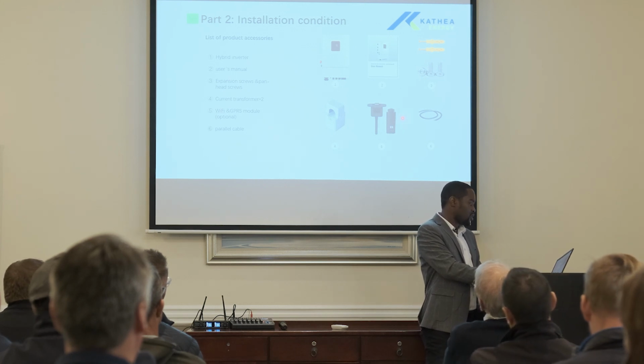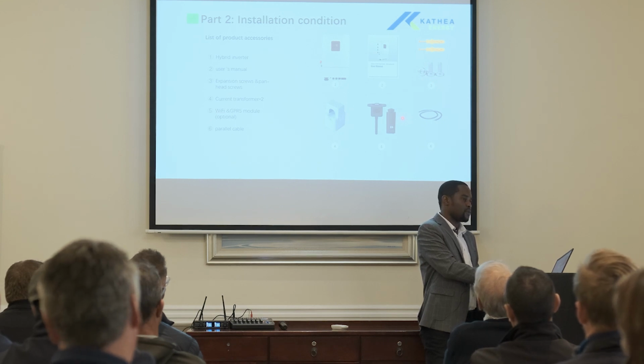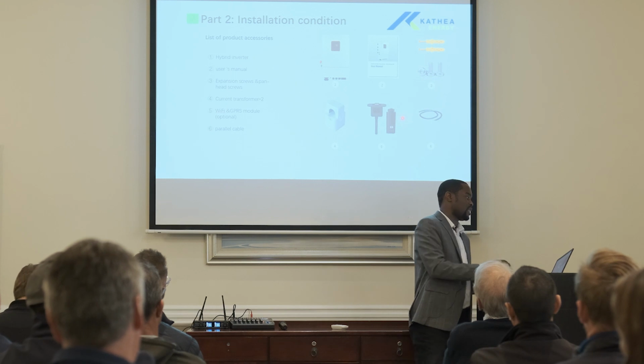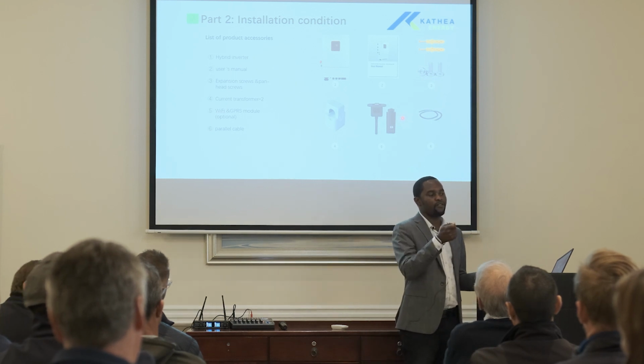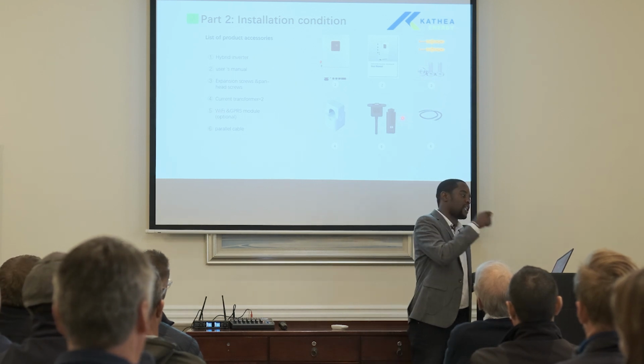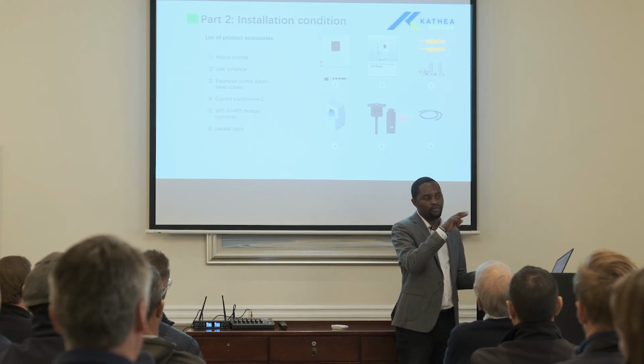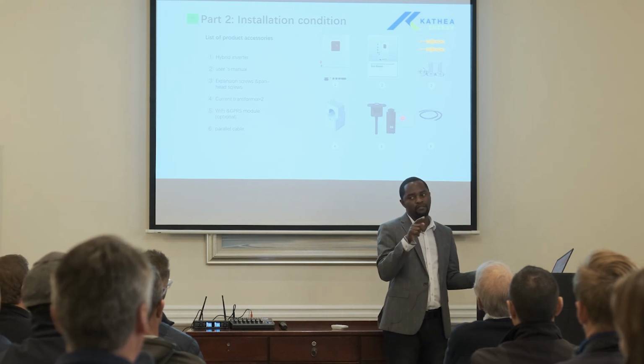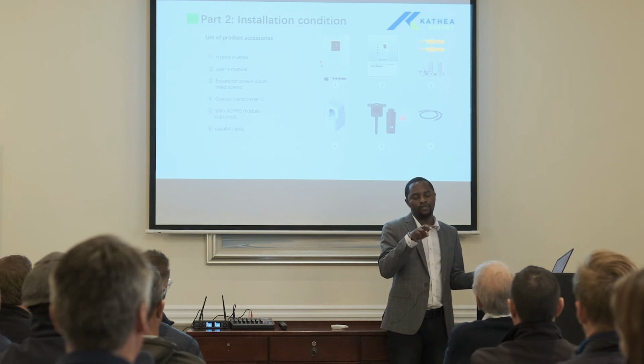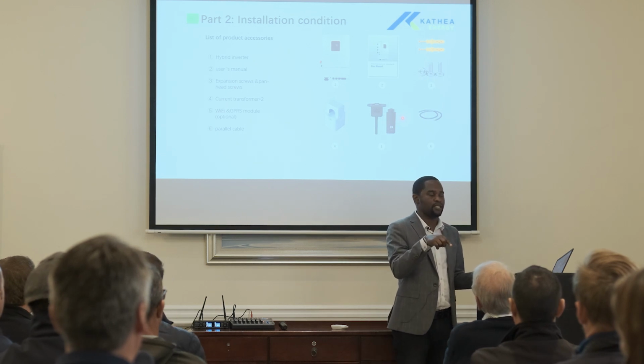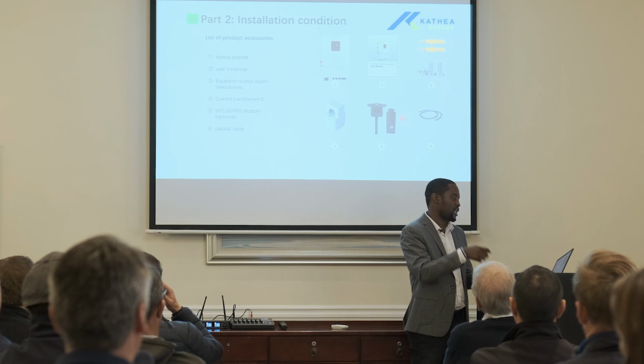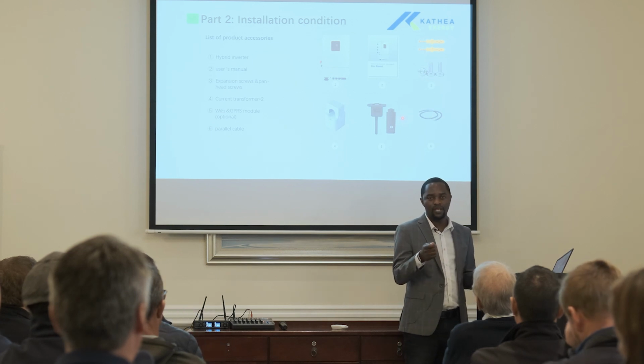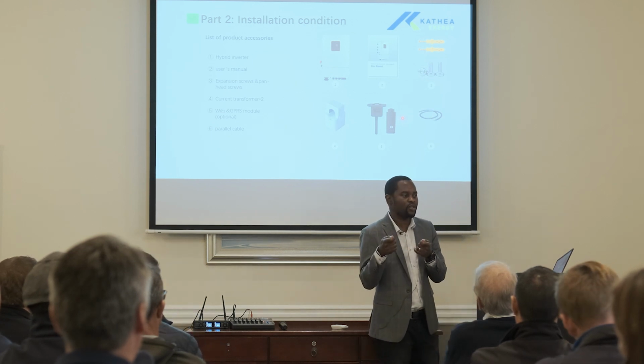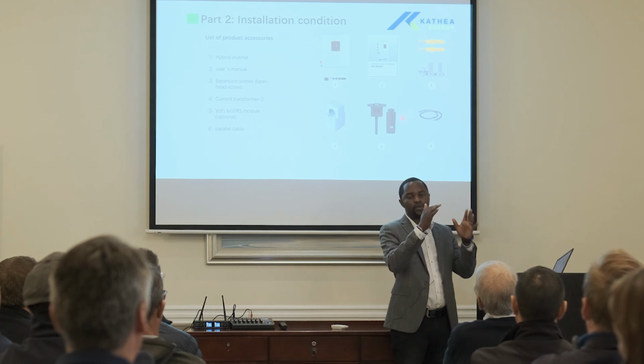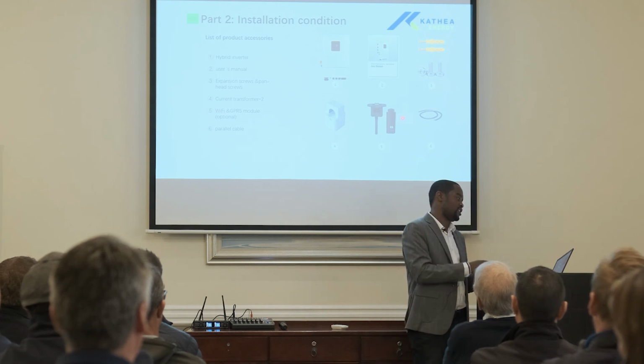Then the expansion screws, everything to mount is provided for. Then you've got current transformers, your CTs. So the CTs are there. The interface for the CTs is RJ45. So you're going to plug it on an RJ45 port, which is a bit different from the normal one that we have, where you've got two wires that we need to connect for the CTs. This one is an RJ45 plug. You just plug it in. So you are not worried about which terminals you are connecting on, because it's an RJ45 plug which is written CT. Then you plug it in.